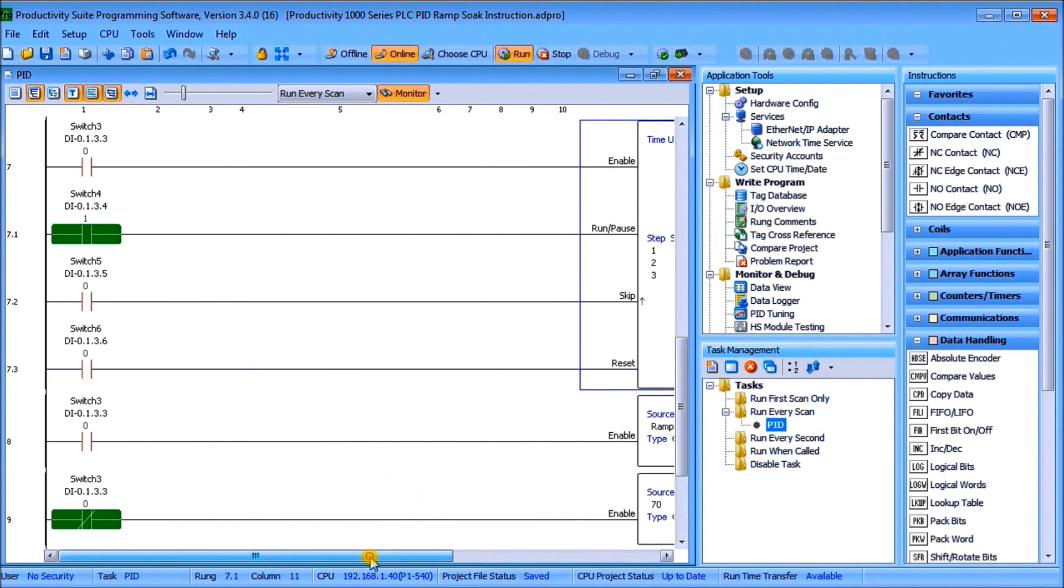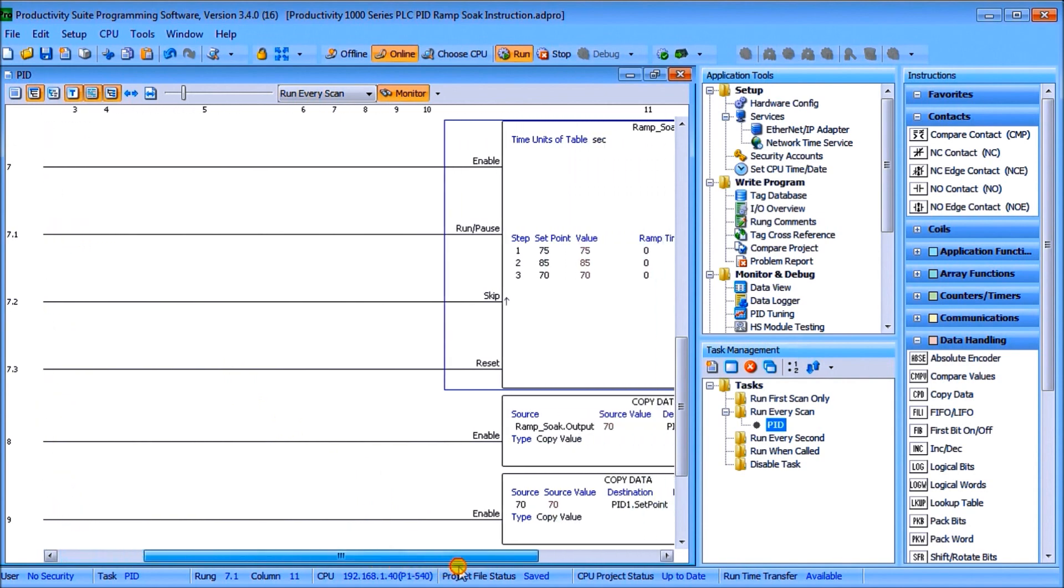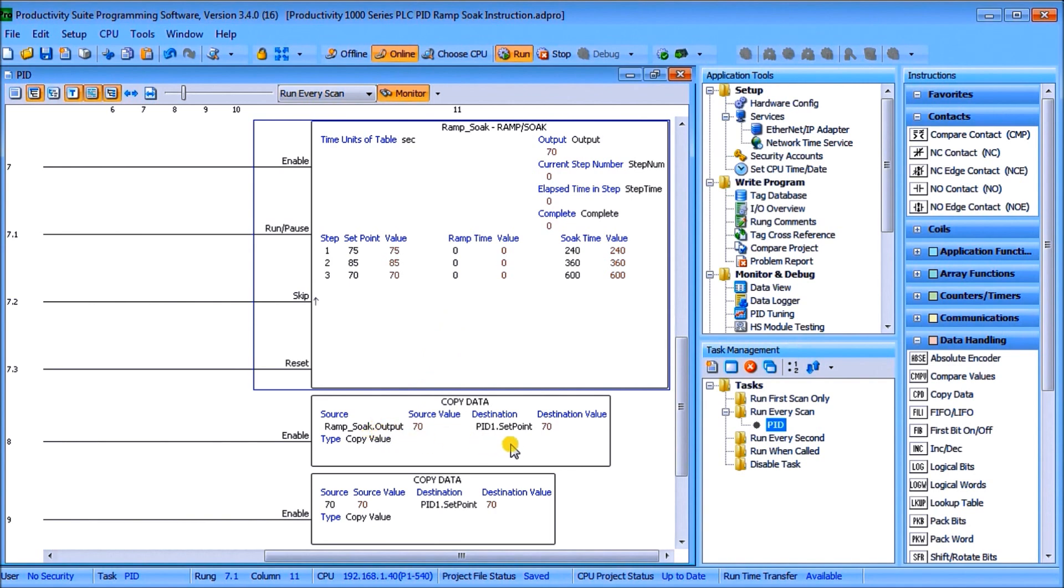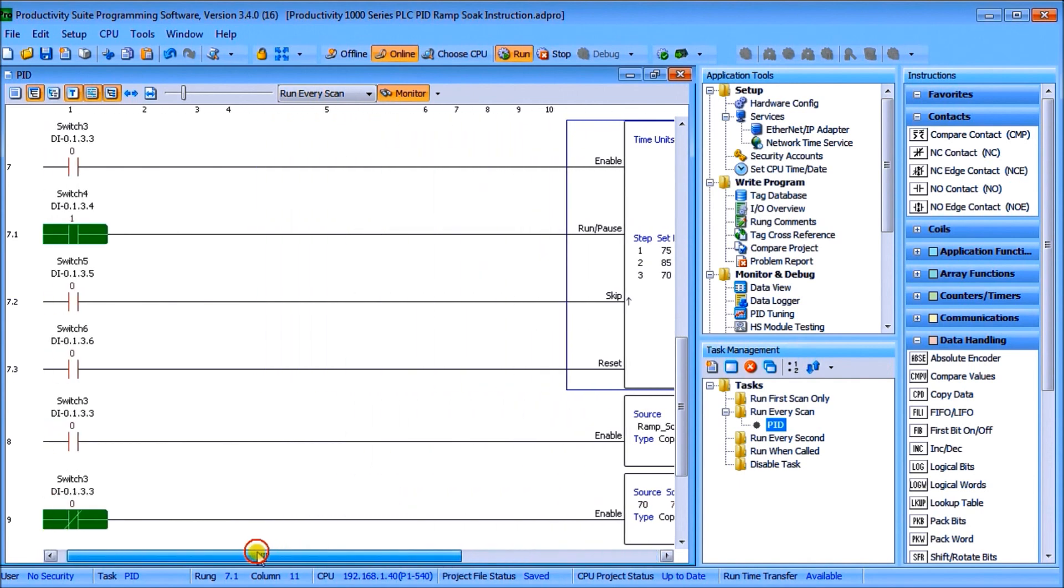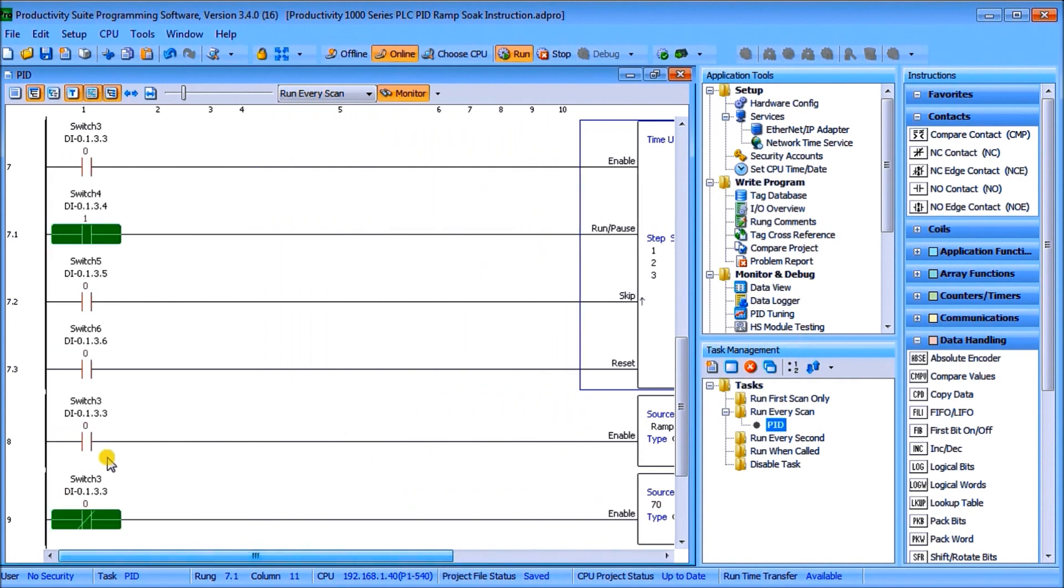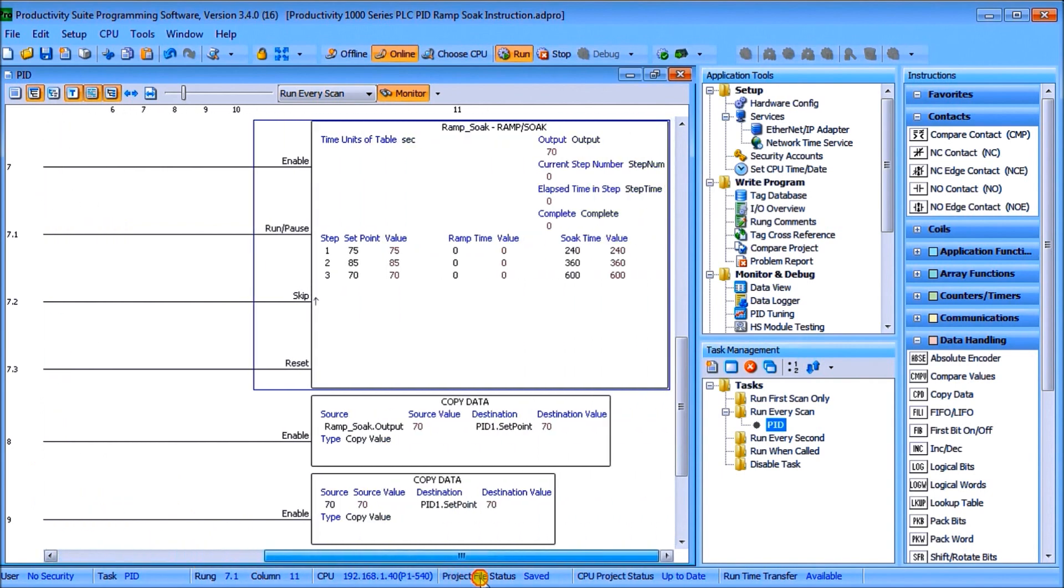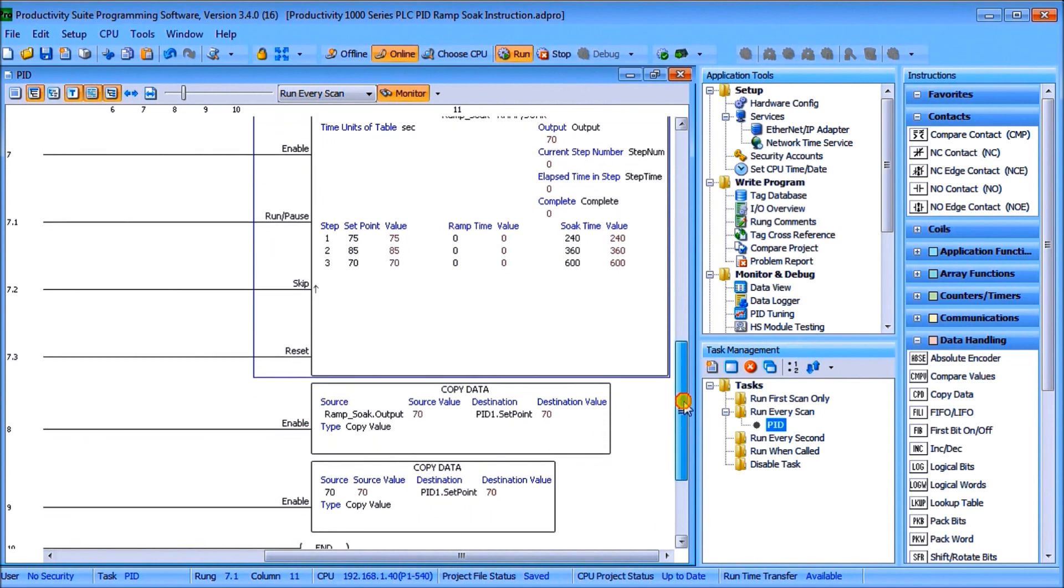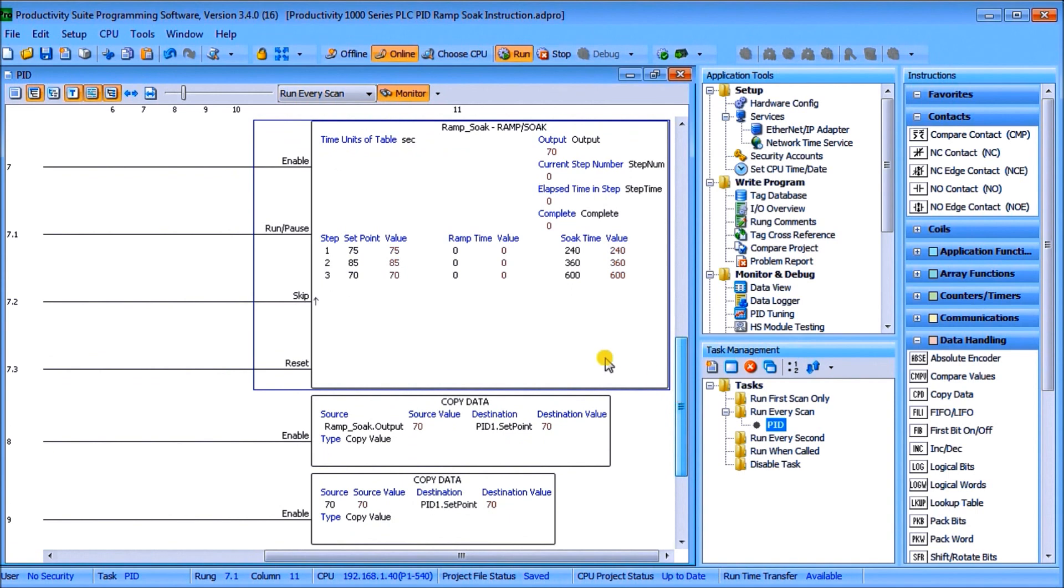Then at the bottom here we have switch number three which will do a copy and so when we're enabling the ramp soak time what we'll do is we will copy our ramp soak output to our set point output. And then if we don't have switch number three on, what we'll do is we'll just keep our PID set point at 70. So that is our program that we've modified and the next thing we'll do is take a look at our hardware.